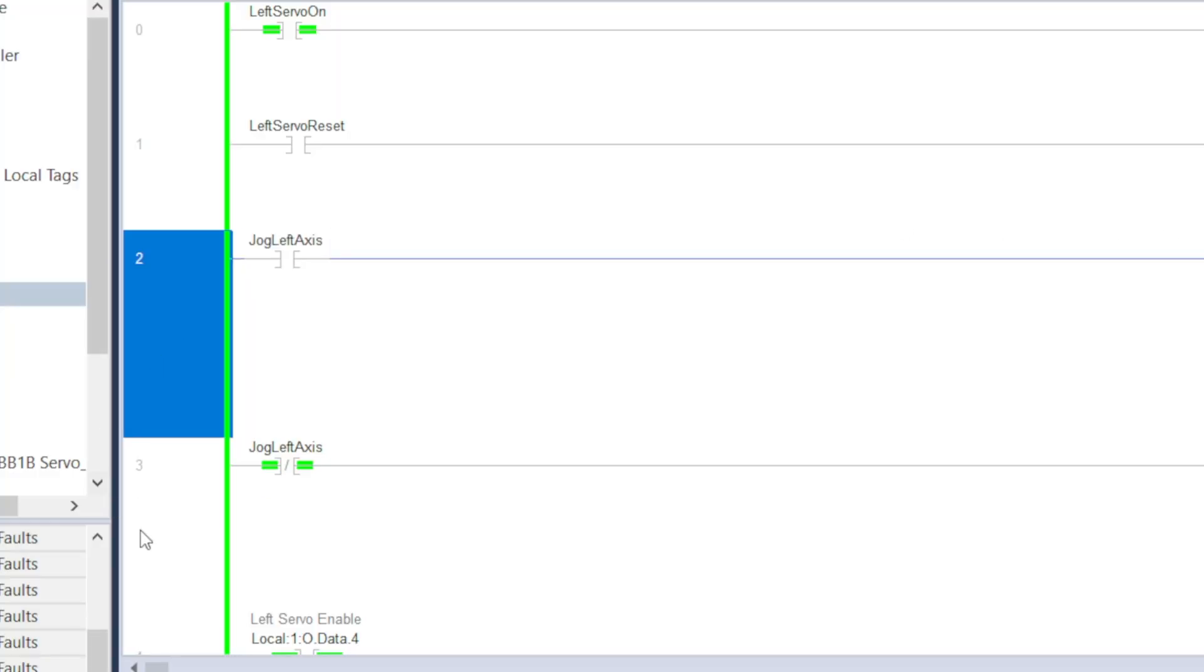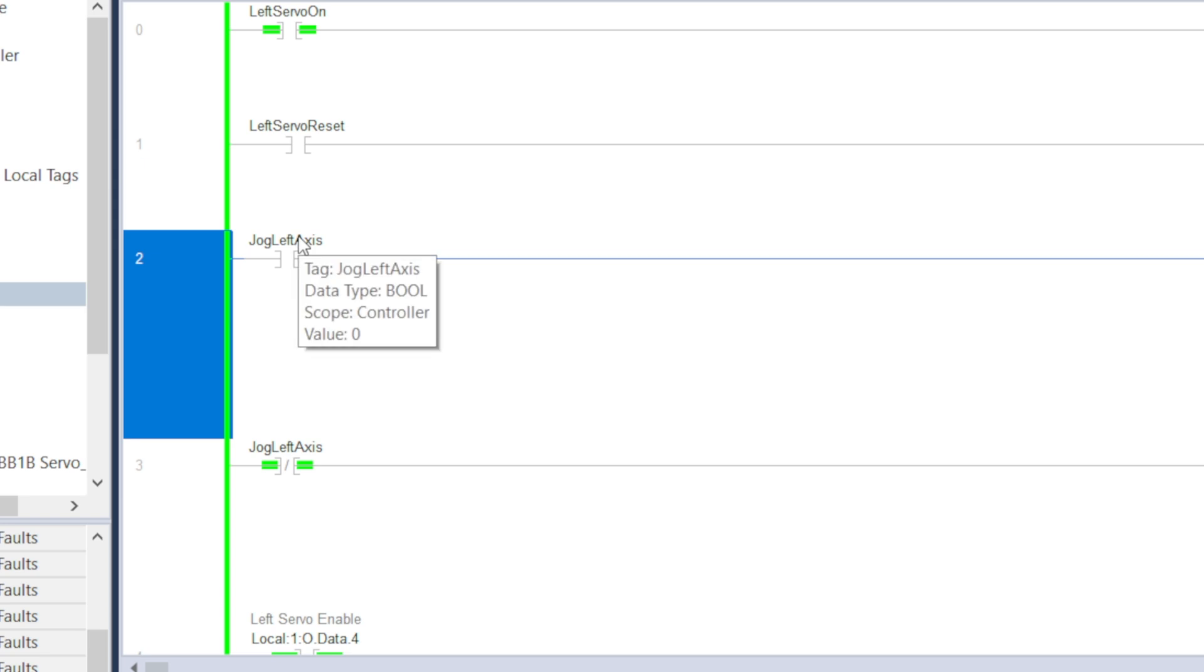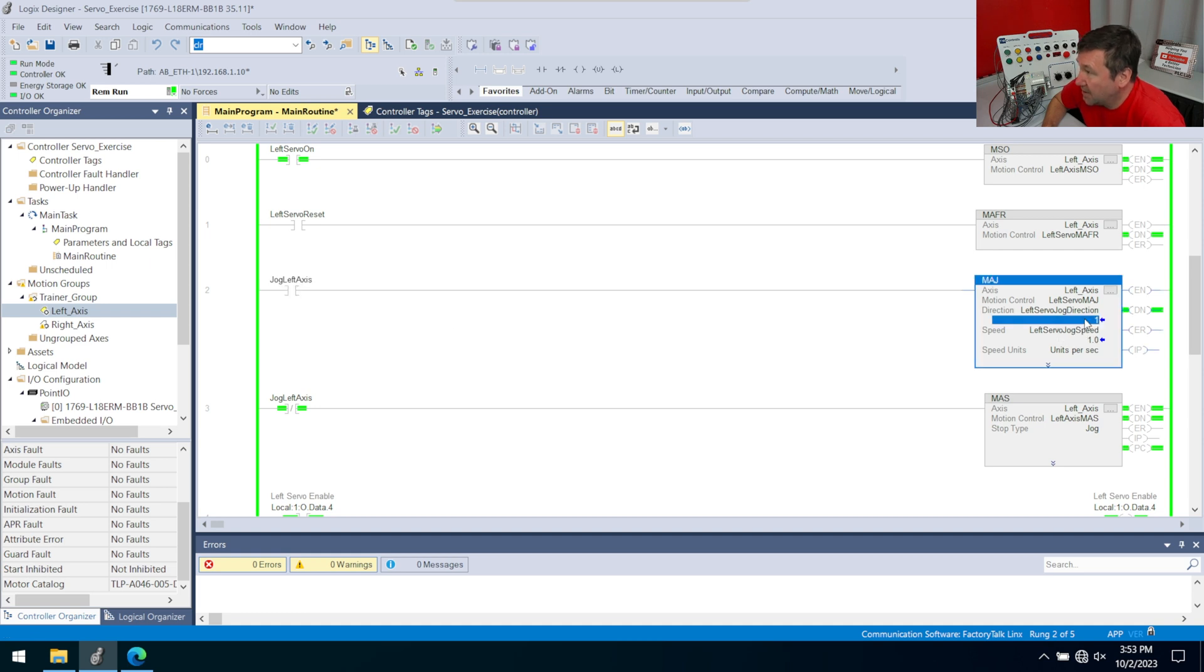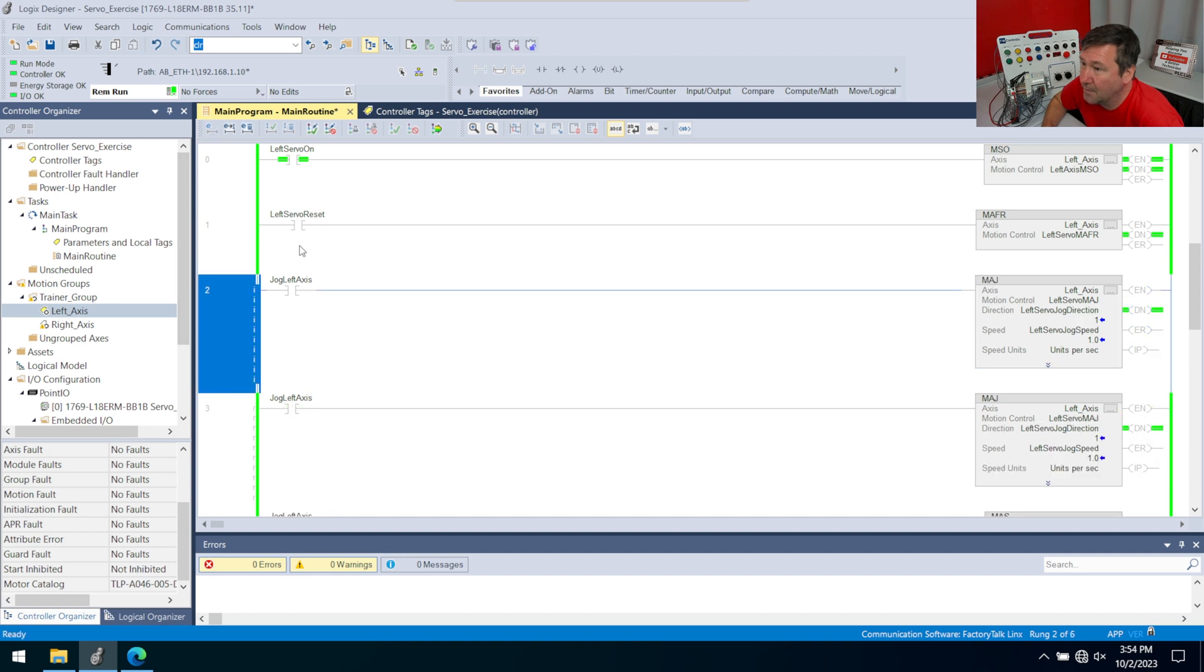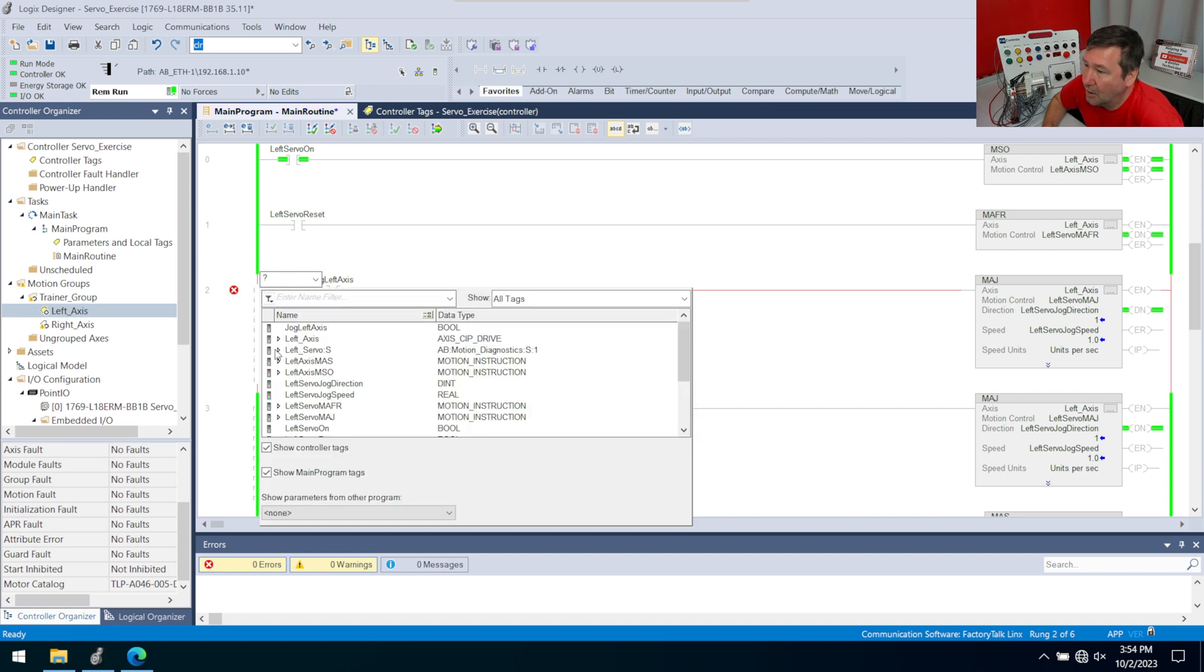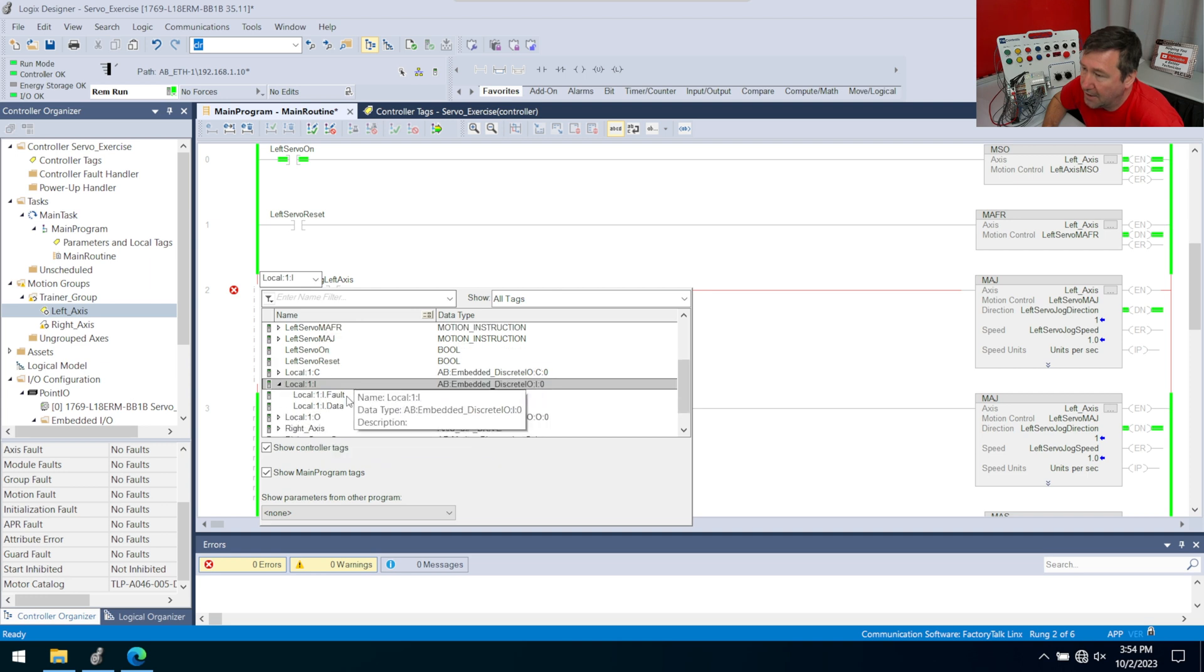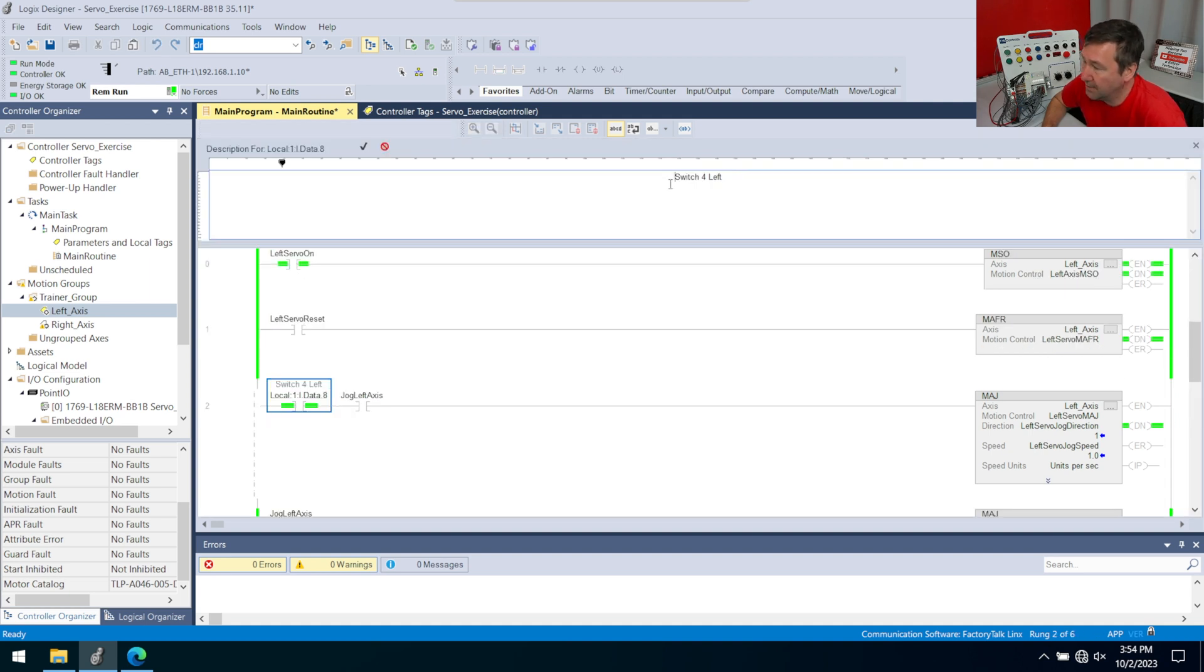To do this, we're mainly going to be modifying these two rungs. So we have our left axis jog. Well, now that's going to be if switch4 is in the left position, and then if either the green button or the yellow button is pressed. Let's go ahead and start a rung edit here. Let's bring down a go look for a one, and let's go and find local colon one colon I, because that's going to be our embedded discrete IO. Then we want data, and then hit our drop down. We are going to want input three. That's going to be switch4 to the left, and we're going to use that for hand. So let's go ahead and modify the description even, and let's call this hand.